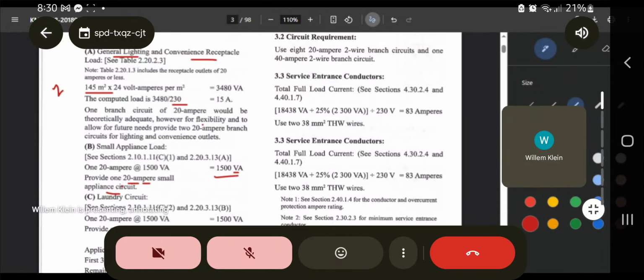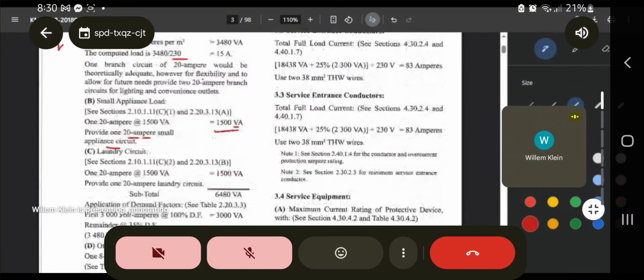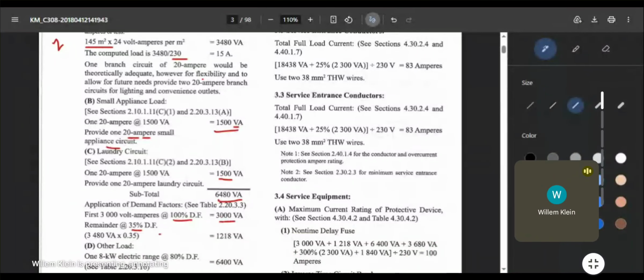Okay. And then for your laundry circuit, the usual rating for the laundry circuit is another 1500 VA. So your subtotal now for your convenience, lighting, and your small appliance loads is 6480 VA. Again, this is already in excess of 3,000. So we will apply the demand factor of 100% for the first 3,000 and then 35% multiplied by the excess of the 3,000.